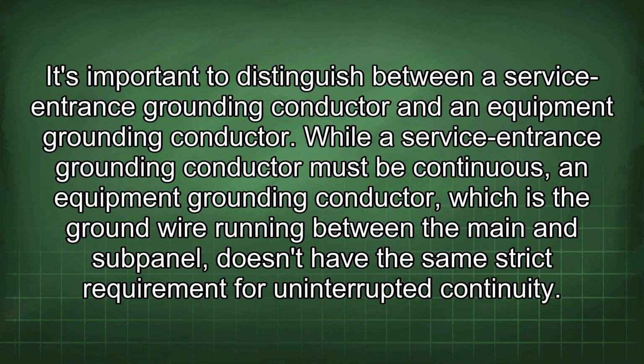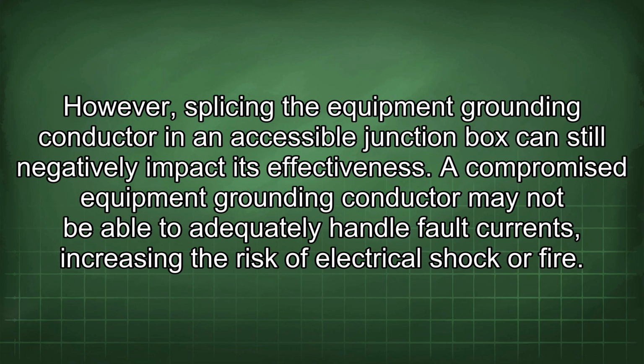It's important to distinguish between a service entrance grounding conductor and an equipment grounding conductor. While a service entrance grounding conductor must be continuous, an equipment grounding conductor, which is the ground wire running between the main and subpanel, doesn't have the same strict requirement for uninterrupted continuity. However, splicing the equipment grounding conductor in an accessible junction box can still negatively impact its effectiveness. A compromised equipment grounding conductor may not be able to adequately handle fault currents, increasing the risk of electrical shock or fire.